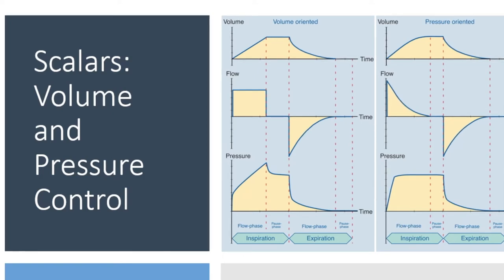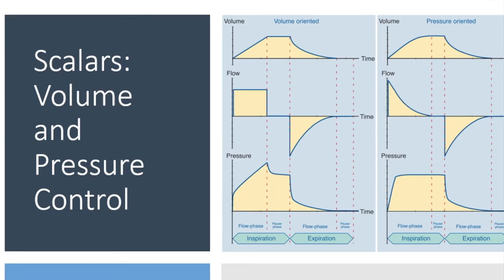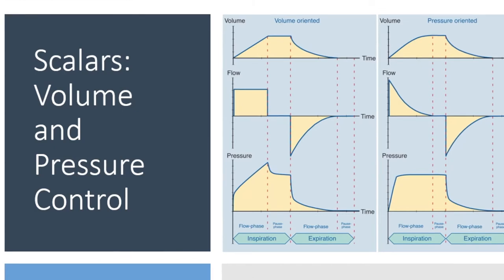With the continuous flow, when there's no flow that's where you get your plateau pressure. You can see the flow gradually increasing the pressure to reach the peak inspiratory pressure. The period of no flow coincides with what we call the plateau pressure, before you then cycle into expiration and get reverse flow, with pressure dropping back to the value of PEEP.